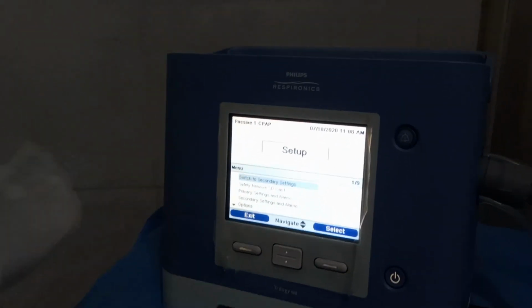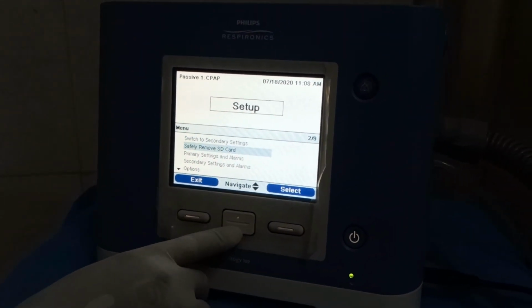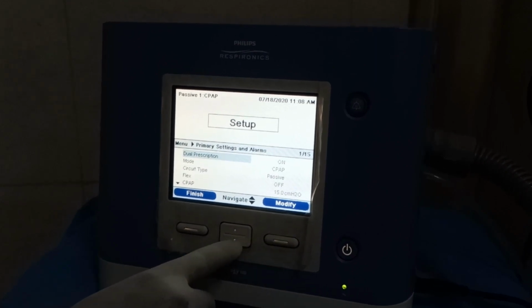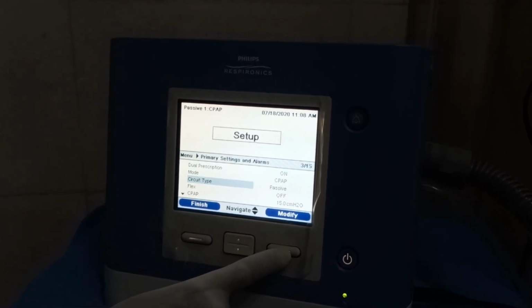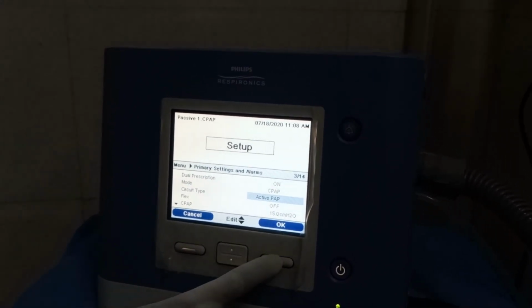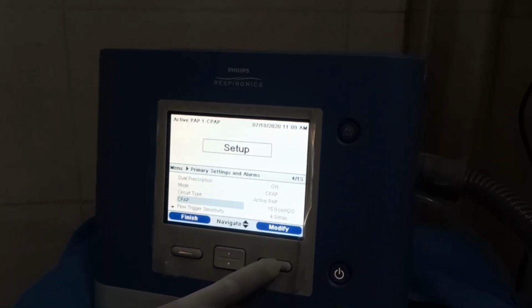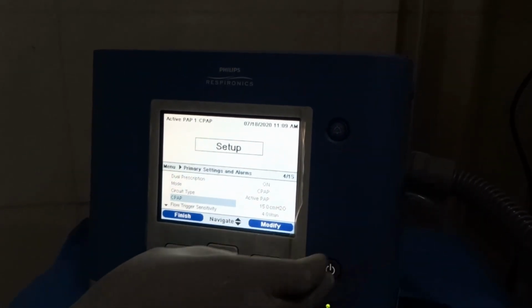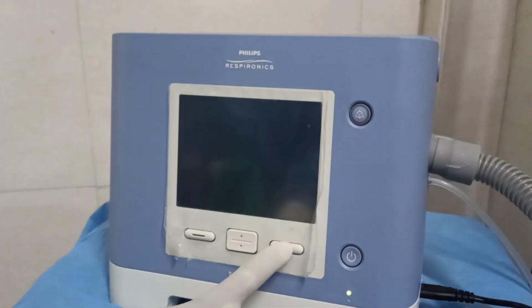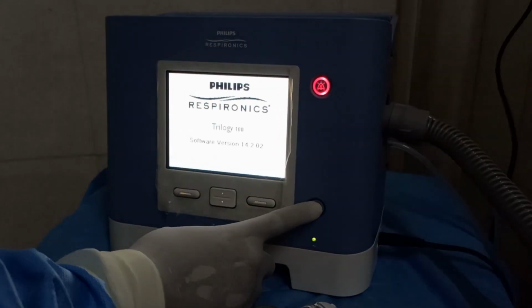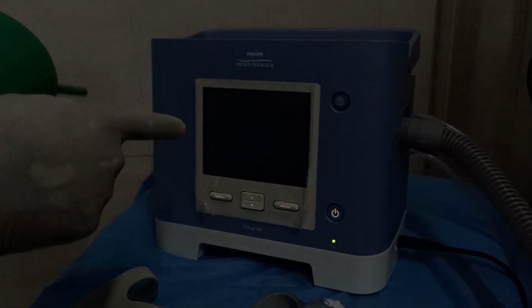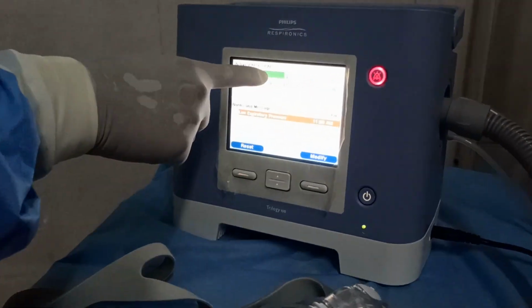It will come up like this. So change the settings, the primary settings. I changed the circuit type, modified it into active. Now it is active type. And I will switch off. Once you change the settings, switch off and switch on again. Now when I switched on, it changed into active type CPAP ventilation.